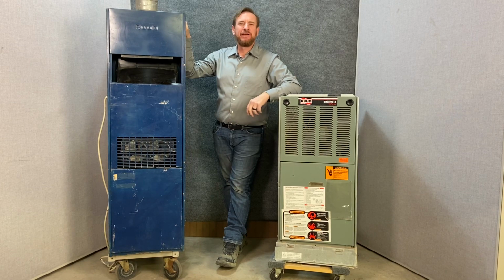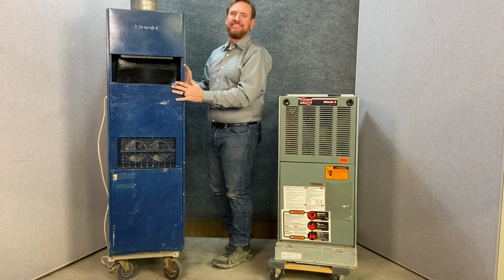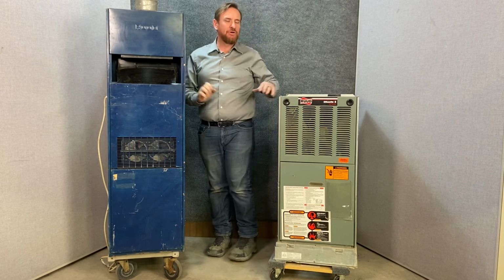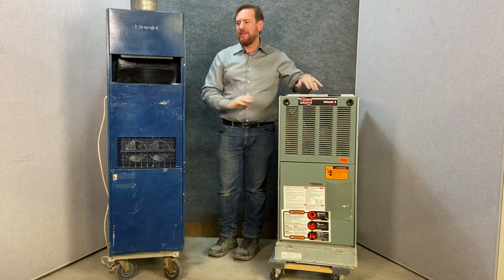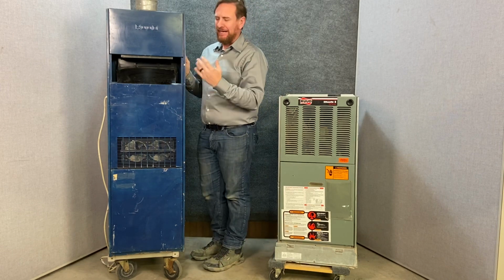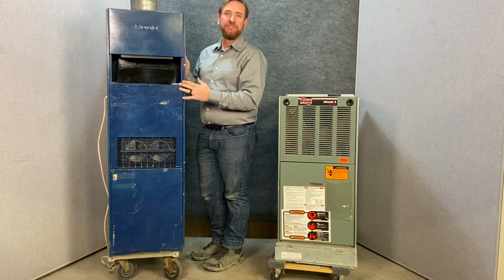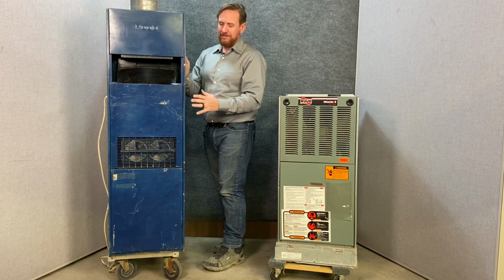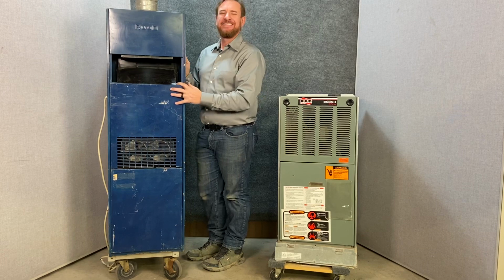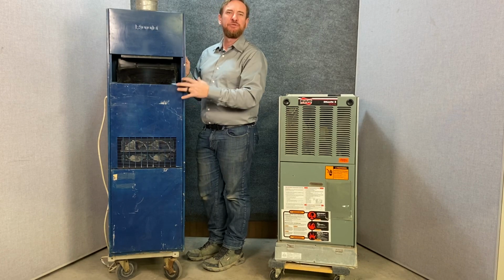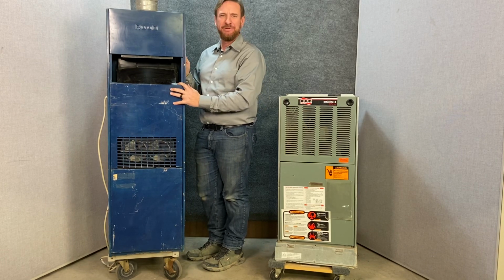In this video, I want to compare some of the differences between an old standing pilot gas furnace and a more modern direct ignition gas furnace. This furnace is a standing pilot, so the pilot light's burning all the time. So that pilot light's burning using a whole lot of gas, whether you're using this system or not. This system with the standing pilot was used up to about 1991, maybe 1992, before regulations changed and they said, hey, you can't put these in anymore.